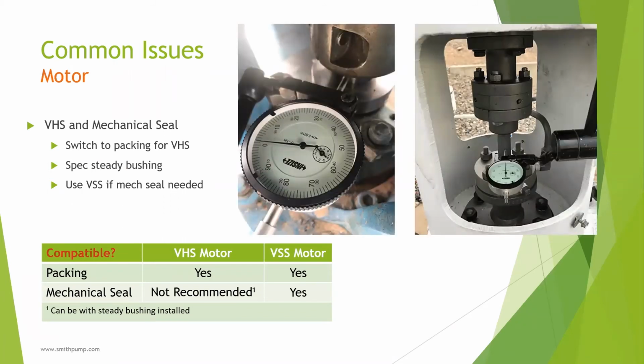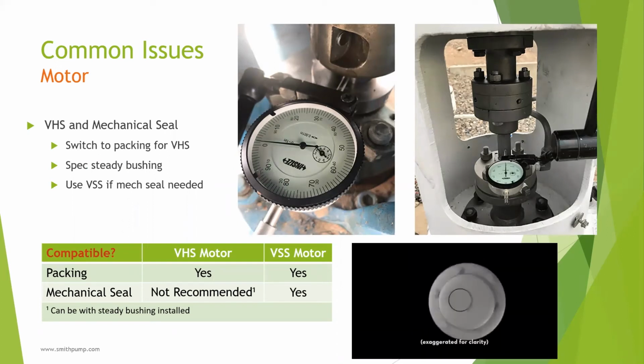So runout is the amount of movement the shaft has in the seal area. So here's an exaggerated picture of the shaft movement if viewed from the motor side. The top picture shows the shaft runout measured with a dial indicator. So our general rule of thumb is shaft runout no greater than 0.002 of an inch per foot when using a mechanical seal, or 0.005 of an inch with packing.